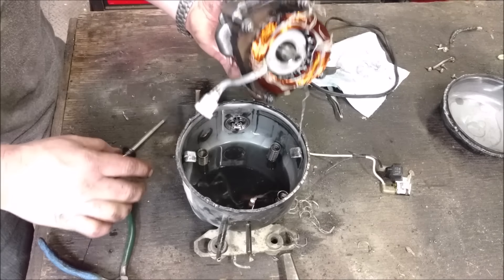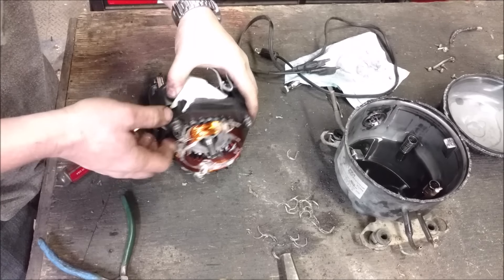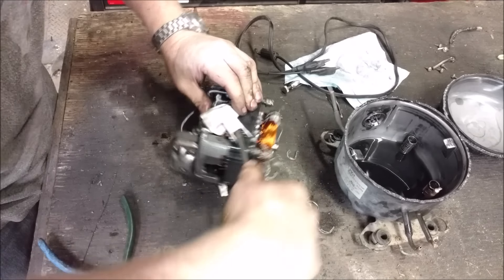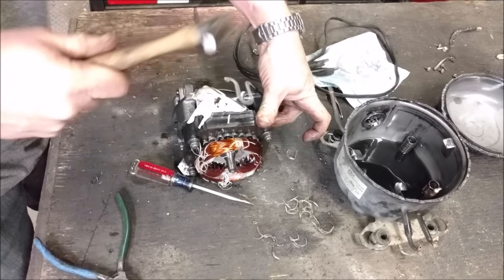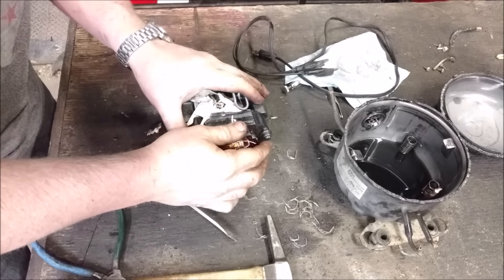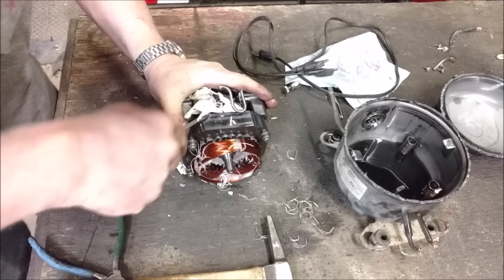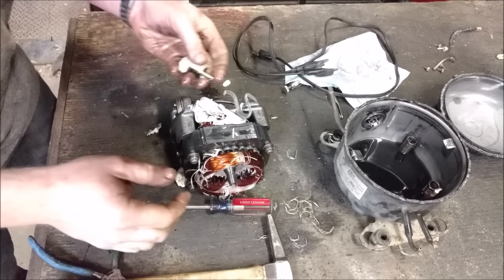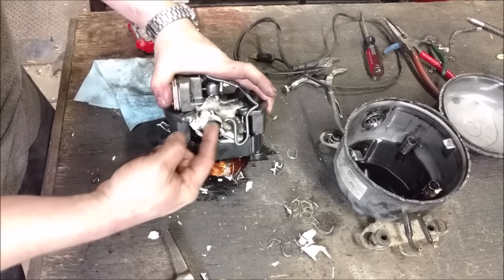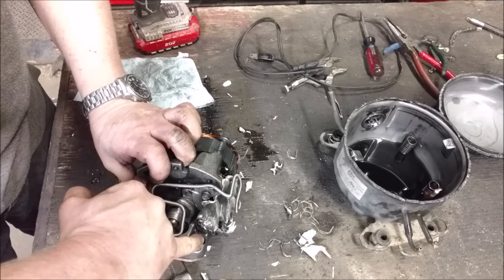This should just be plugged on in here — yep, it's plugged in. And then we should be able to remove our air filter intake right here, pry this off. These windings are crunchy. I got off as much as I could — it's just completely melted into the windings. It would just inlet into this hole, so this would be your inlet, and then this little hose is your outlet for the compressor.